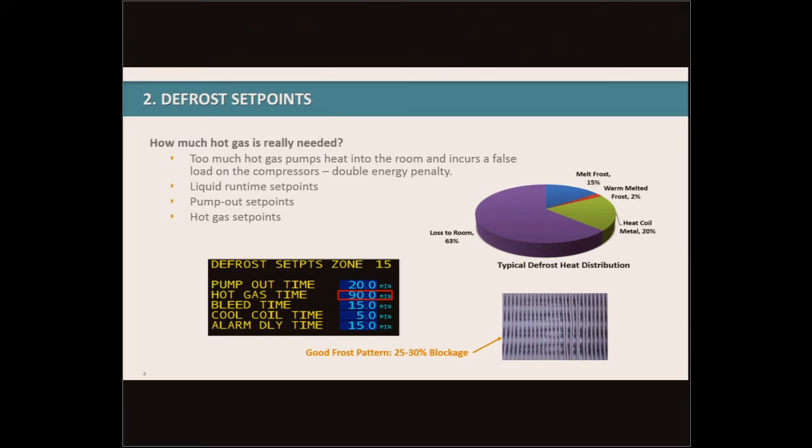So a couple red flags to look for here. In the control system screen, you see this is a red flag with the 90 minutes of hot gas. Typically, if a hot gas cycle is over 20 to 30 minutes, that's a red flag that there's some other issue that needs to be addressed. And by no means 90 minutes would be needed for a hot gas. The other photo we have here is for a good frost pattern. Evaporators will build frost. Having frost on an evaporator is not a bad thing. We just need to make sure that we limit how much frost is built onto the evaporator before we send it into a defrost. So a good rule of thumb is observe the evaporator. And once 25 to 30% of the spacing between the fins is occupied by frost, that's a good initiation to start the defrost cycle.